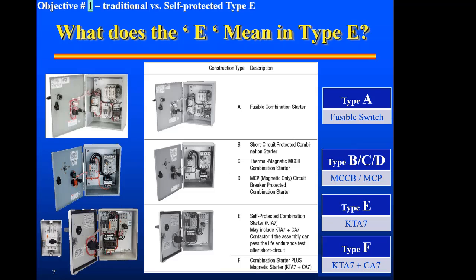Then we get down to Type E and F. Okay, Type E is what we're highlighting today, and that sure, a Type E self-protected combination starter, it can comply, and we'll talk about how and why. But it may or may not include a contactor. If you don't need an external signal, and if you are okay with manually walking up to the device, then yeah, KTA7 by itself complies with self-protected Type E. Then, as in a description of Type F, now we're adding on a CA7 contactor as in a Type F. So, hey, there's a letter code for this, and this is what Type E really categorizes as.